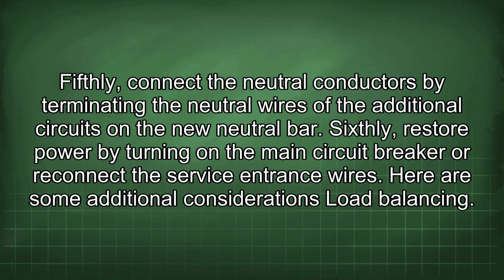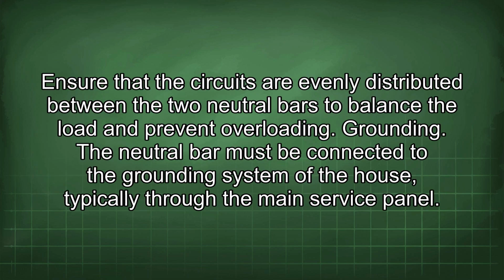Fifthly, connect the neutral conductors by terminating the neutral wires of the additional circuits on the new neutral bar. Sixthly, restore power by turning on the main circuit breaker or reconnecting the service entrance wires. Here are some additional considerations. Load balancing: ensure that the circuits are evenly distributed between the two neutral bars to balance the load and prevent overloading.